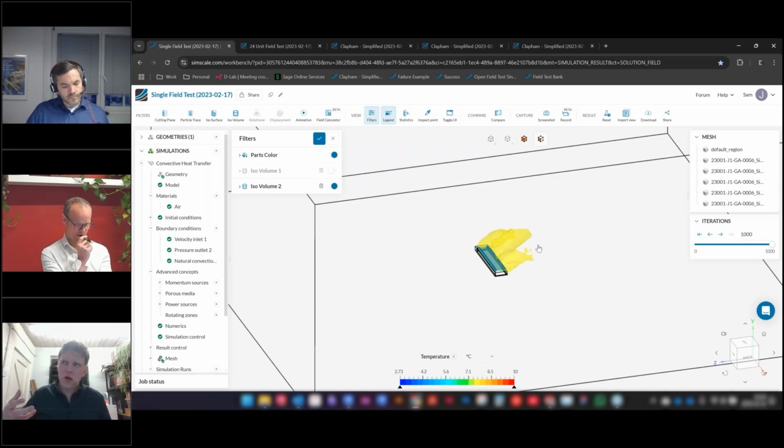But also importantly, we're comparing the outcomes of this with the data sheets that we get from the suppliers and the manufacturers of the heat exchangers. So is what they're saying what we are seeing in our simulations? Not to say someone's incorrect, but we need to make sure that those two pieces of information are paired together before we move on to the next stages.